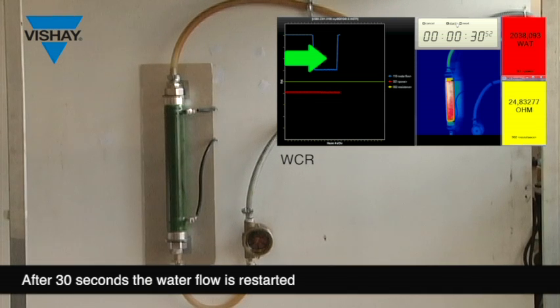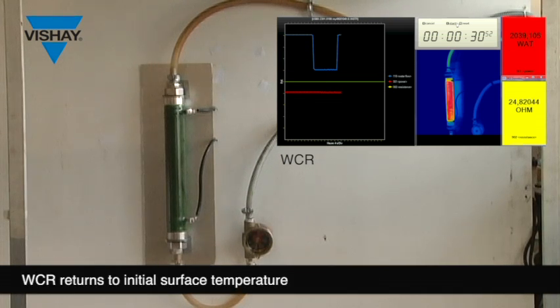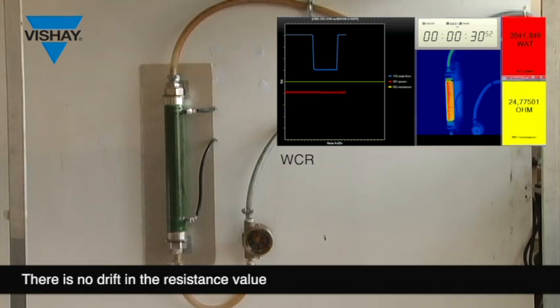After 30 seconds, water flow restarts. WCR returns to initial surface temperature. No drift on the ohmic value: 24.77 Ohm. No destruction or leakage of the resistor.